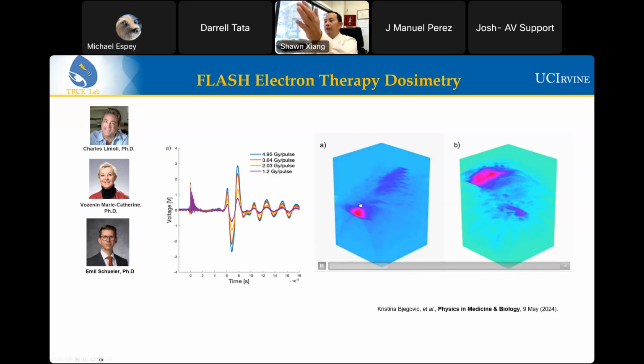Figure A is the flash electron beam in water. You don't see much fluctuation in the water for the electron beam, but the one on the right is the electron beam in an animal, and you do see a lot of variation in each pulse. That might be because of the electron beam itself, and also might be the different heterogeneity of the animal with different tissue types. But anyway, we can measure a single pulse in flash therapy. I think that would be a very important tool to verify the dose being delivered to the patient, eventually to accelerate the translation of flash therapy.